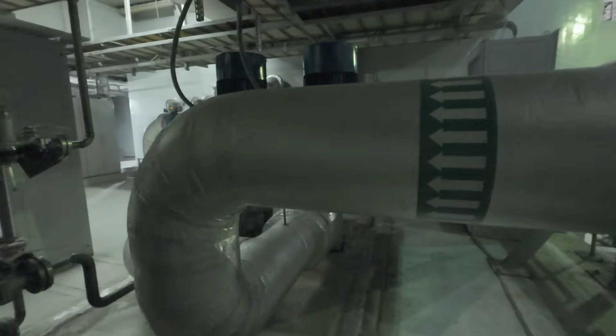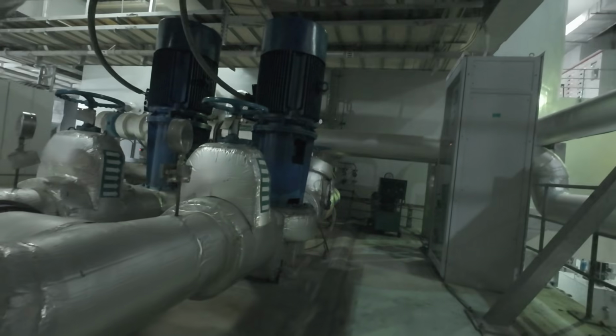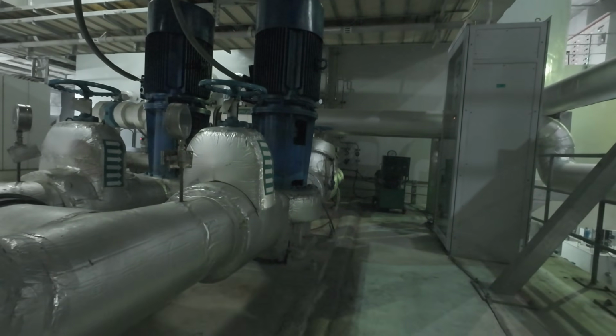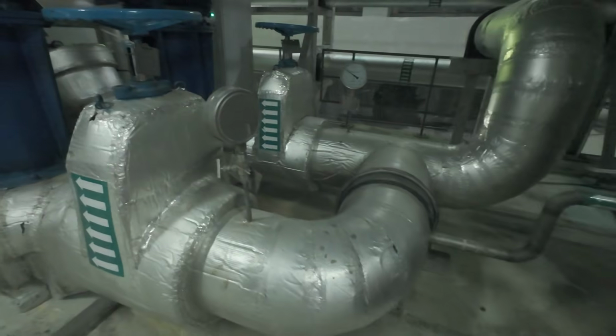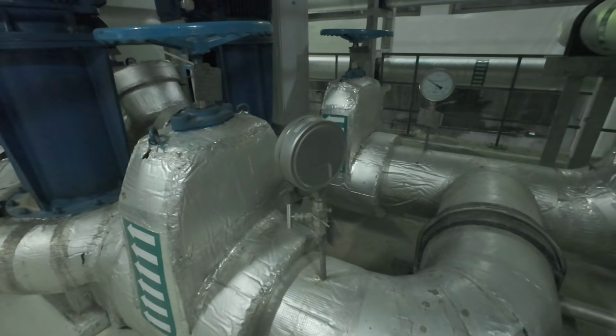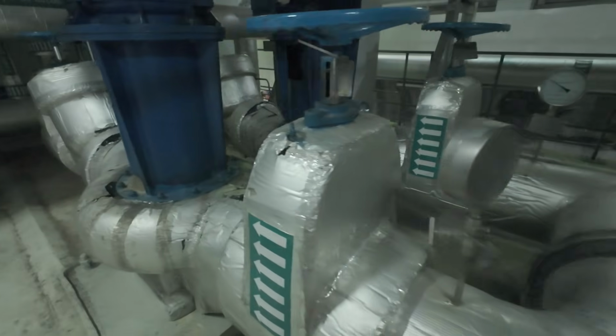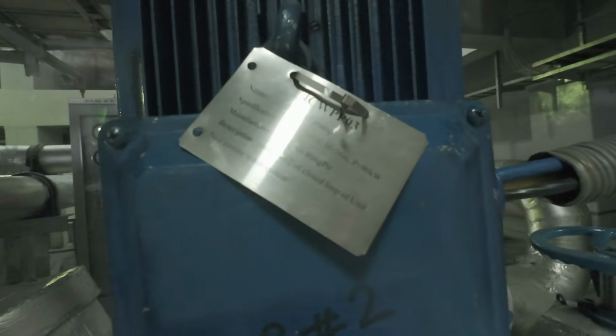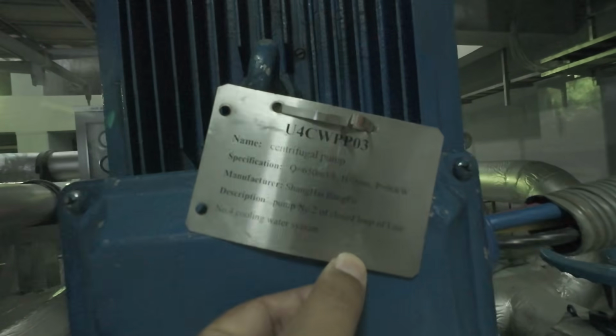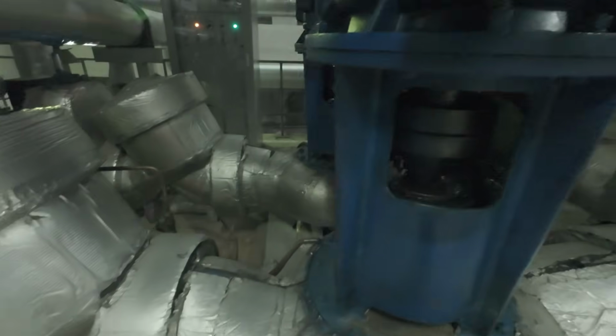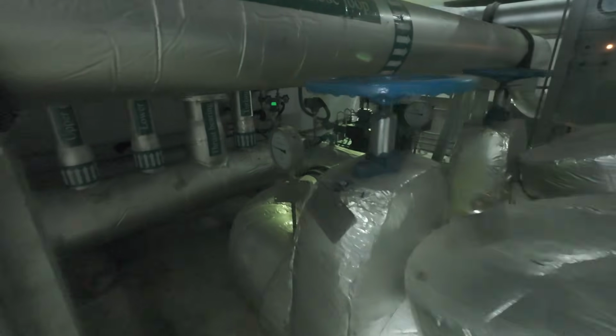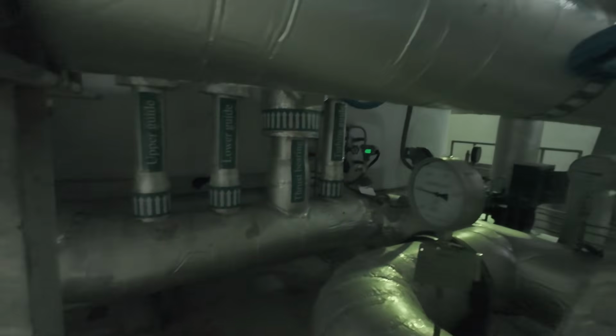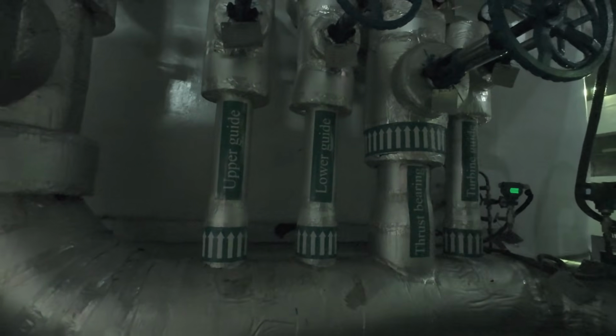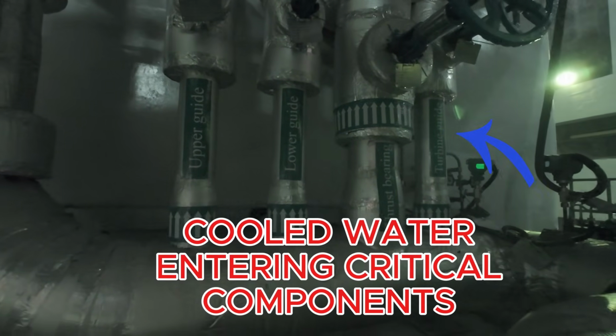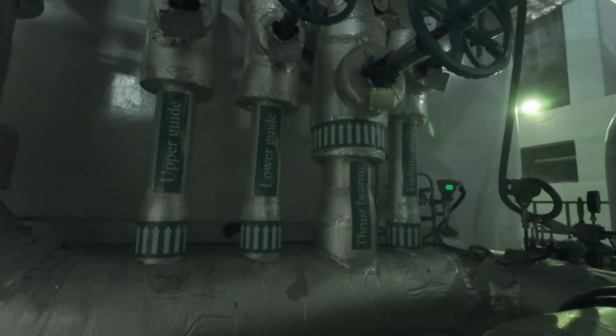But what happens if cooling suddenly fails? This is where the protection system becomes critical, because sensors continuously monitor water pressure, temperature sensors monitor bearing temperature, cooling water temperature, generator cooling performance, and if temperature rises too high, alarms activate immediately. If cooling pressure drops dangerously low, the unit may automatically trip to prevent catastrophic damage. And if the main cooling pump fails, the standby pump starts automatically within seconds. Even the strainers are monitored for blockage, because one blocked line can threaten the entire hydropower unit.